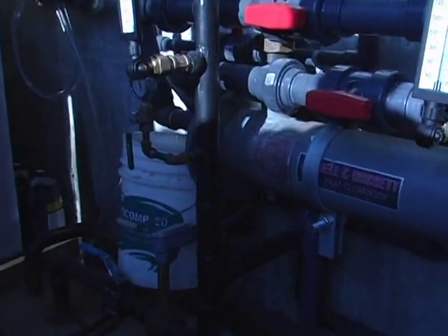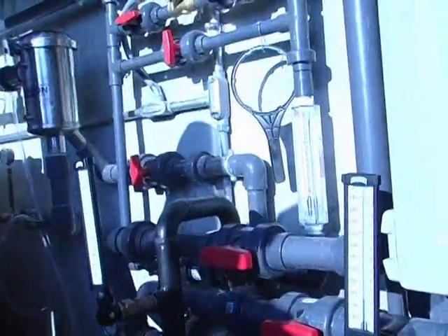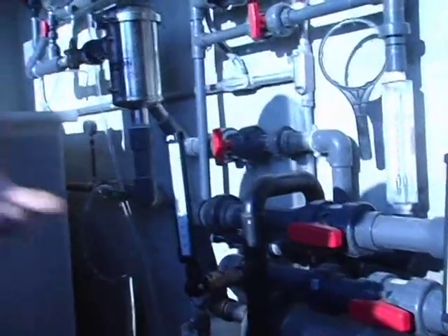When you need higher temps in the humidification chamber, this valve opens and flow stops going this way. It now goes into the heat exchanger and will come out of the heat exchanger and back out of the building. So just say your temperature is 60 degrees desired in that chamber. This valve is tied to a temperature probe down there, which sends a signal back to SCADA, and this valve will regulate on its own until it achieves that desired temp.